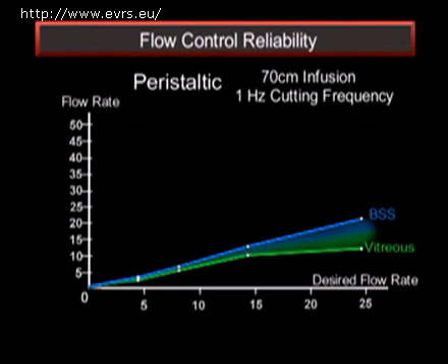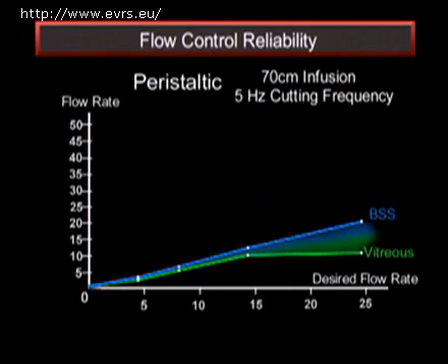In contrast, with a peristaltic pump, up to the point where the machine will not be able to provide the required depression, the operator can almost perfectly control the flow, whatever the cutting frequency is.